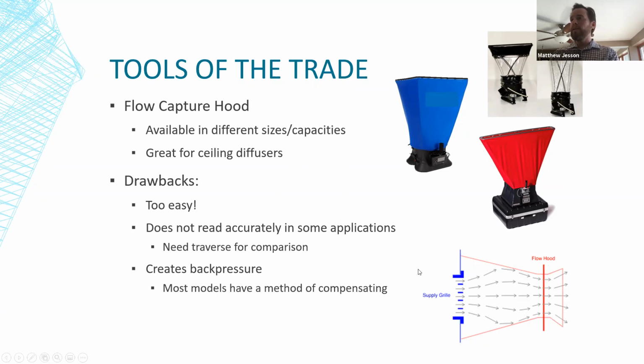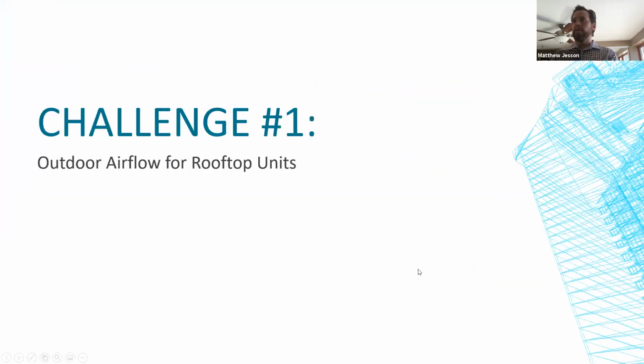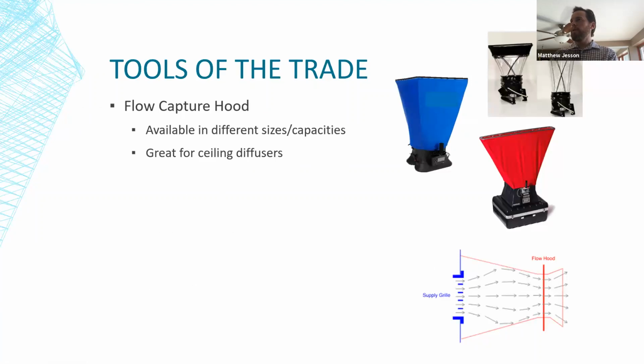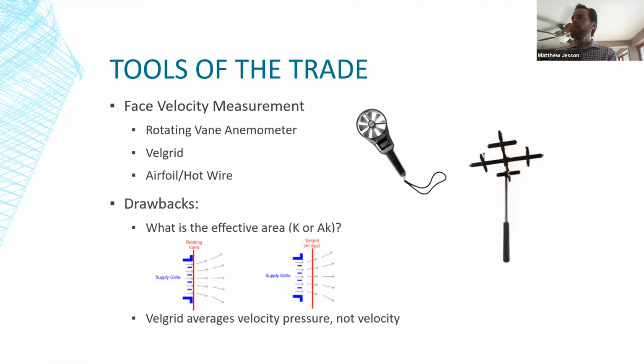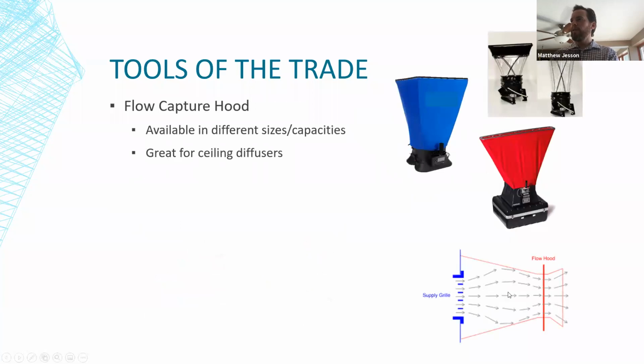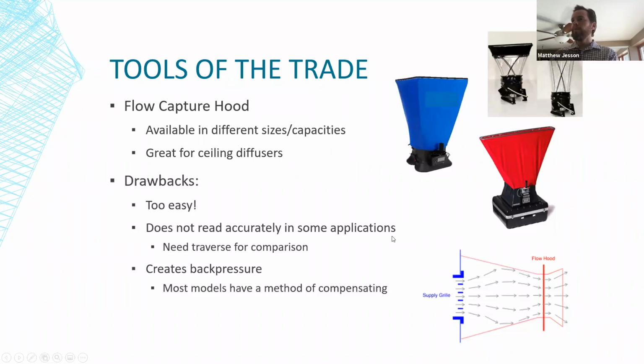And the measurement device in the flow hood is typically, going backward here, something a lot like this VelGrid. That's what's in the base of the hood. It directs the airflow across that and is attached to a meter that's located on the hood base that goes through an algorithm essentially to calculate the flow.